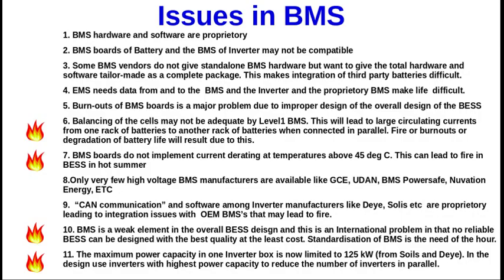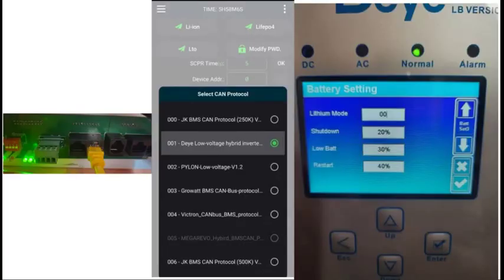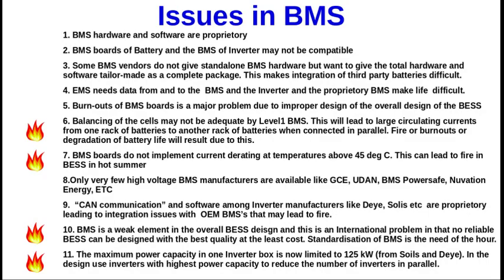Point number 7. BMS boards do not implement current derating function as a function of temperature above 45 degrees C. This can lead to fire in BESS in hot summer, particularly if the CAN signaling link to the inverter is not functioning. Point number 8. Only very few high voltage BMS manufacturers are available, like GCE, UDAN, BMS PowerSafe, Nuvation Energy, etc. Point number 9. CAN communication and software among inverter manufacturers like Deye, Solis, etc. are proprietary in nature, leading to integration issues with OEM BMSs that may lead to fire.